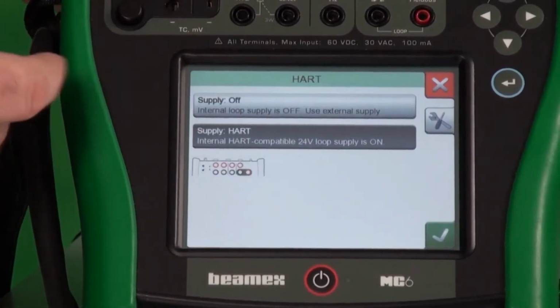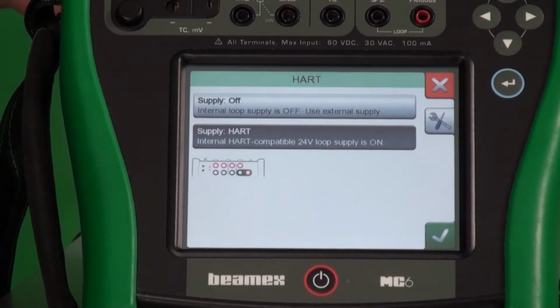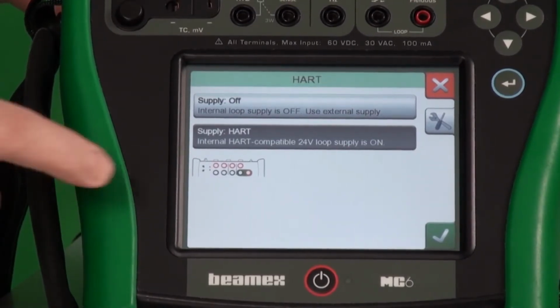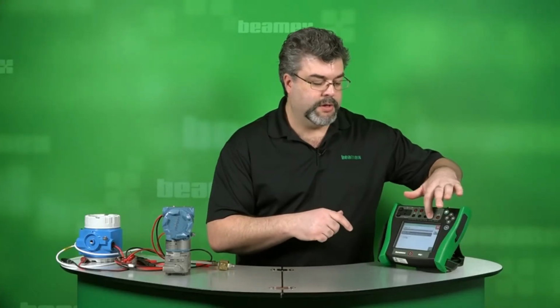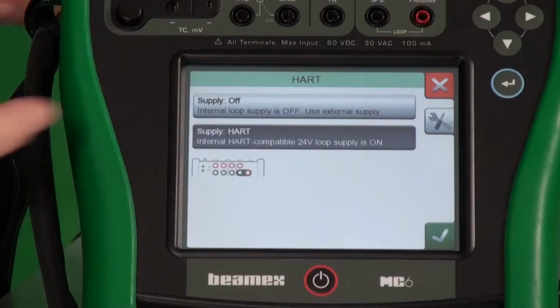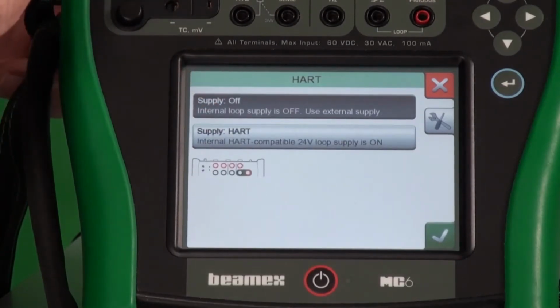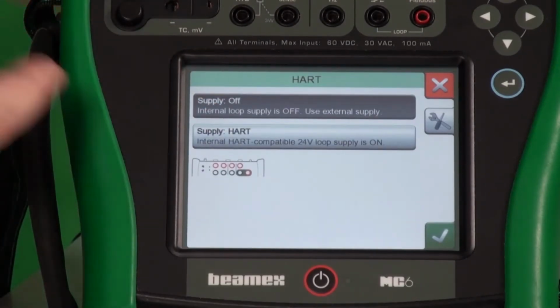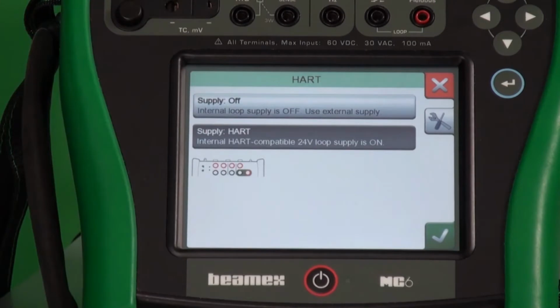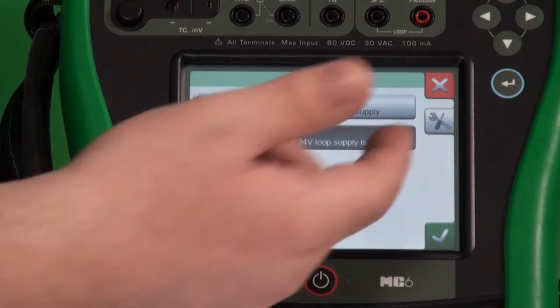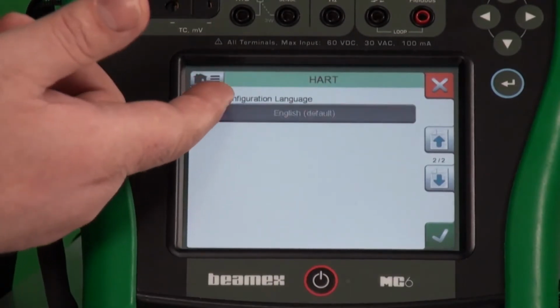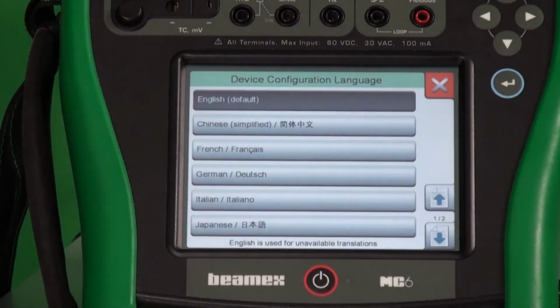With HART, it lets us know where to connect. So we'll hook up the output of the device right here, which is these two. And this is also where the loop power supply comes from. So you decide whether you're using external power, maybe powered up by the process, or you want the calibrator to provide power for that. Maybe you want a different language. So instead of English, maybe you want to have one of the other options available.